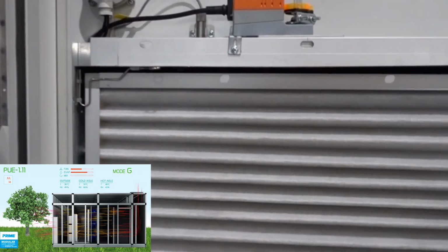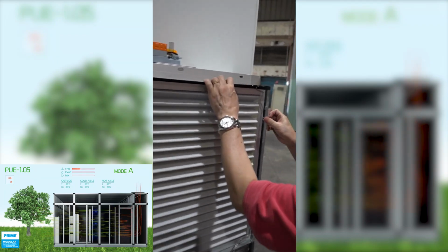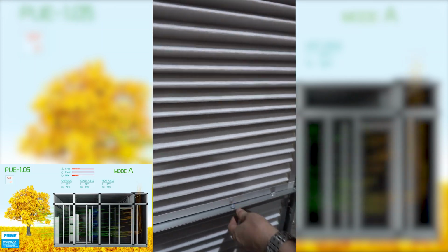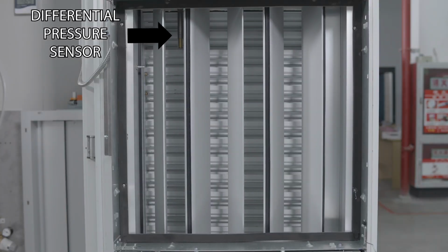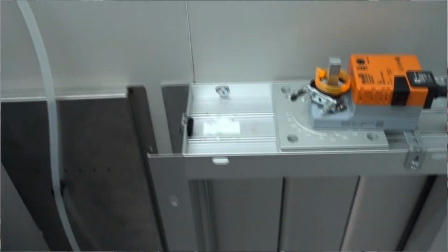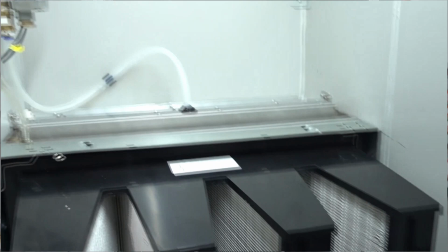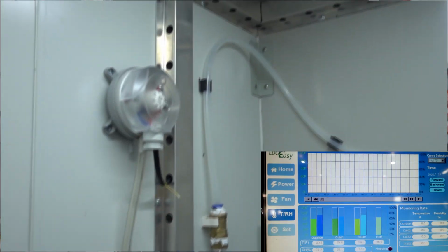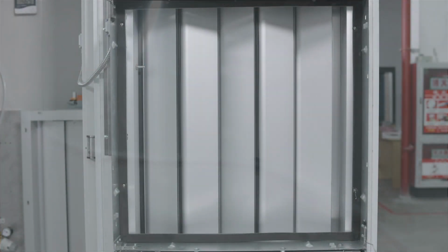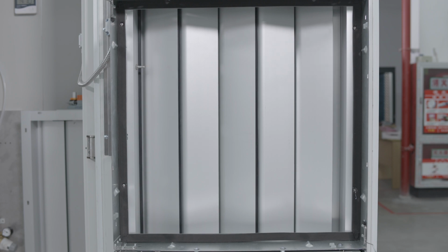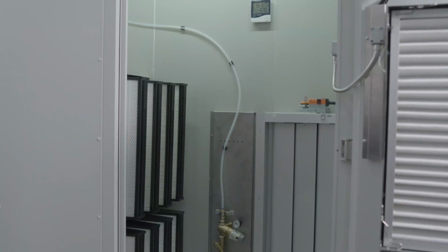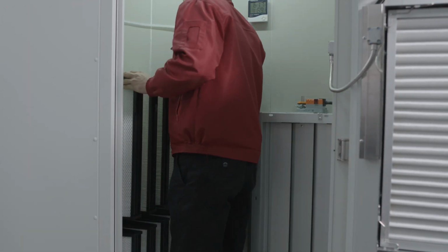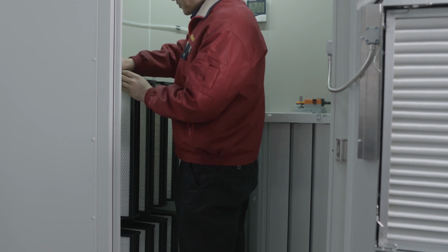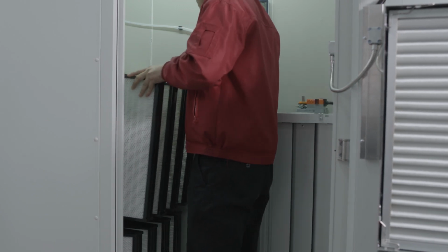Outside air enters the MDC through the intake room. Installed in the door are premium quality grade G2 pre-filters that remove impurities and dust from the air. Differential pressure sensors behind the dampers in the door let you know when it's time to replace the filters. The dampers open and close based on what the sensors tell the control center. There are nearly 100 Siemens environmental control sensors in the MDC, many in the intake room that measure the incoming air temperature and humidity, controlling opening and closing the intake dampers and the recycled air dampers, when it's time to change the G2 air filters, when it's time to change the F8 chemical filters that protect IT equipment from sulfide and nitrogen oxide erosion, how much moisture needs to be added to balance the humidity, it controls the lights, and more.